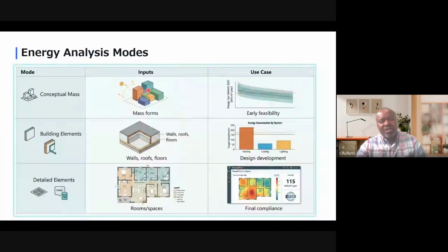So I'm going to have less load to deal with, but the orange building has like 3 or even all 4 faces exposed to sunlight. If I was not modeling based on actual site location and surrounding buildings, and instead applied a rule of thumb calculation, since the floor area and floors are typical, I could calculate for the ground floor and say, okay, maybe I have 100 kilowatts, and apply 100 kilowatts on all the floors. What will be my error? You'll find that the floors at the topmost part will have load higher than 100 kilowatts, because the lower floors have been shaded by other buildings casting shadow on them.